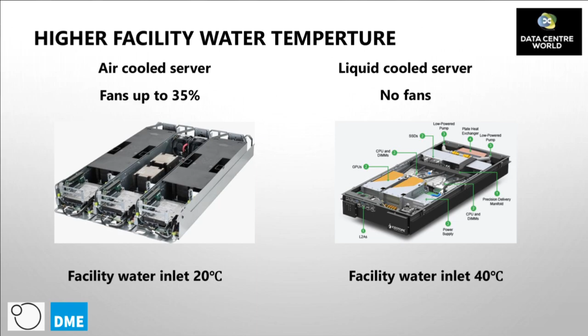25 degrees airflow is used to cool down all the components in that server, provided by the 20 degrees water cooling facility on the data center side. When it comes to the new generation of AI servers, the energy consumption just for the internal fans can rise up to 35%. At the same time, if you look at a liquid-cooled server, the inflow of the liquid can be at 40 degrees, and this is ideal to handle the heat rejection from all components, providing good conditions for making use of the excess heat.